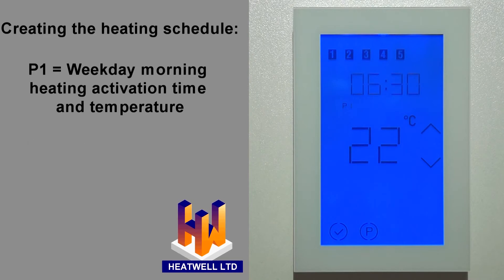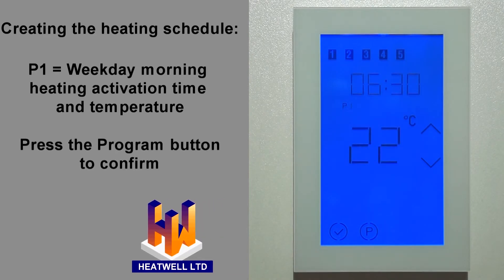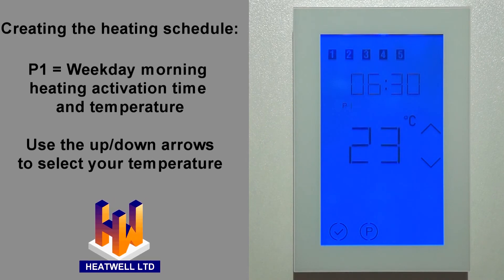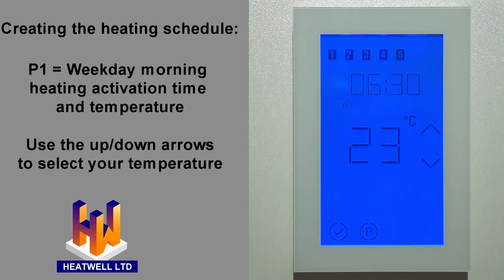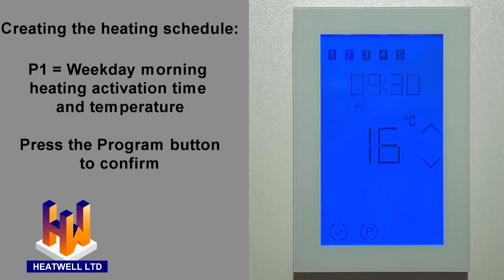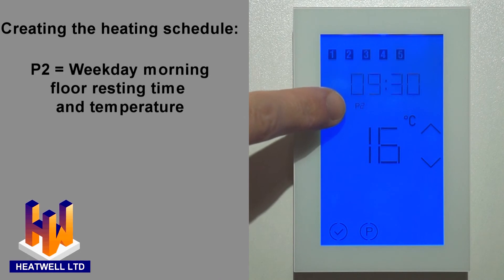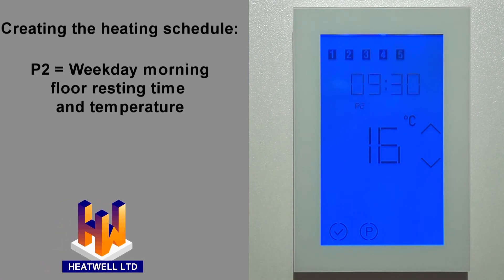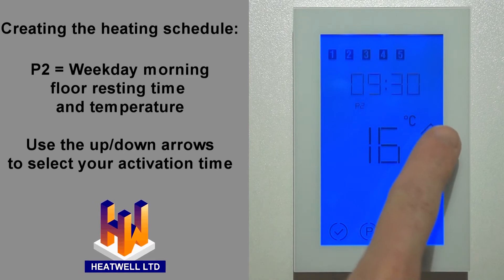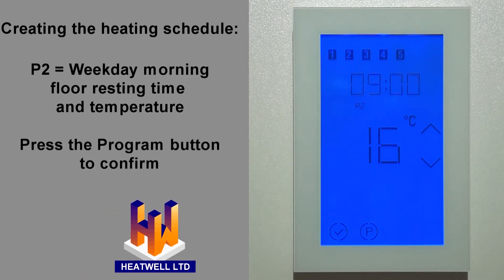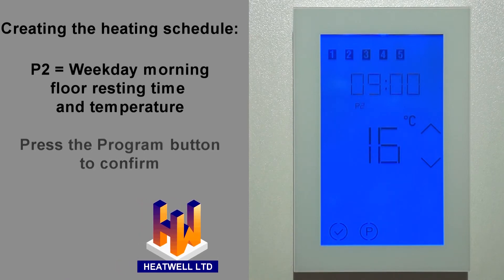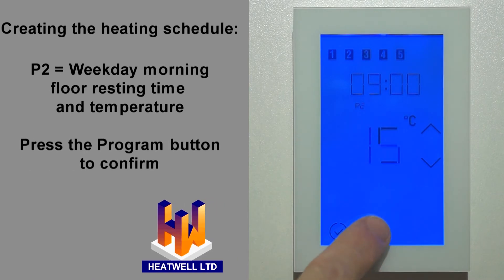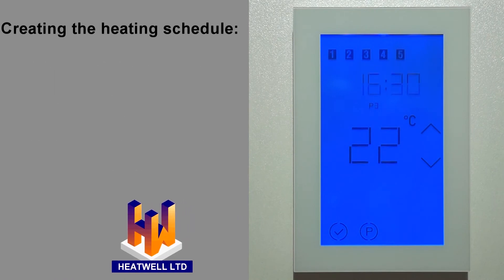When you have your time selected, press the program button. Now we'll select the chosen floor temperature for that time — in this case, 23 degrees. Once you've chosen your preferred temperature, press the program button again. Your first weekday activation time and temperature has been set. Now P2 will be displayed. P2 is your weekday switch off or resting temperature and time for when you've left home to go to work. In this case, we'll select 9 a.m., then press the program button, and then select the resting floor temperature — in this case, 16 degrees. Once you've chosen your preferred temperature, press the program button. The P2 resting floor temperature has been set.